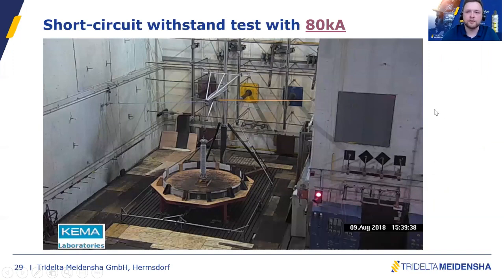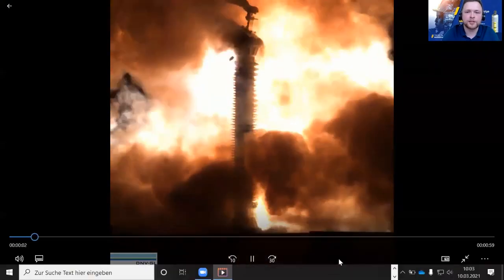And now it gets even more interesting, because we are recording this test with a special camera, a high-speed camera. This is not working as well. We have the link here. And this is about 50 frames per second. So you can see the 50 Hertz wave pulsating. You can see how the current is flowing through the air, through the ionized air. And what we also see is that there is a surge arrester in the middle, and from its structure, it's not destroyed. The membrane is opening, the pressure can release, and the surge arrester is still more or less intact. The housing is not fractured, and this is what we have to confirm during this test.